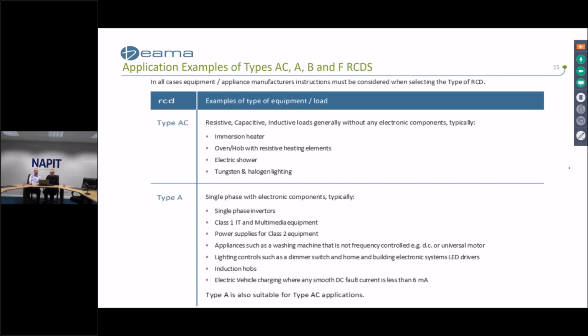So the widely used Type AC RCD provides protection for what can be considered resistive loads. You can see these typical examples listed on the slide. We've got immersion heaters, ovens and hobs with resistive heating elements, electric showers, tungsten and halogen lighting.